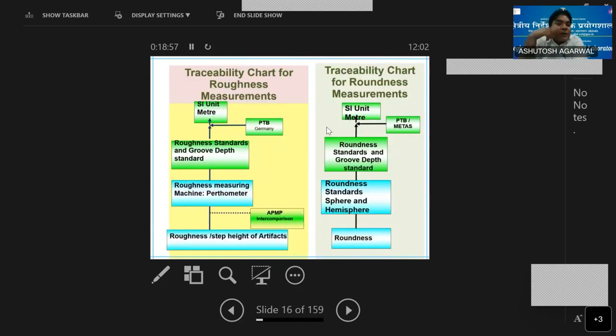Then traceable for roughness measurement. For roughness, we have a roughness measurement machine, based on a semi sphere that we calibrate from METAS Switzerland, and then we calibrate our machine. Whether the same roughness is given by our machine or not. If it's the same, like 60 nanometer, then we calibrate our system, and by that machine we calibrate piston, cylinder kind of things. And this is for roundness also, roughness and roundness.